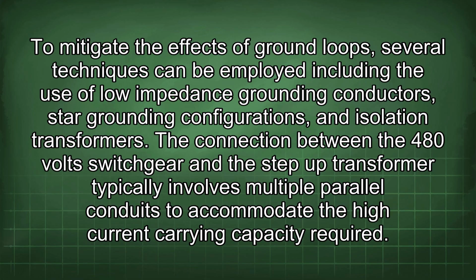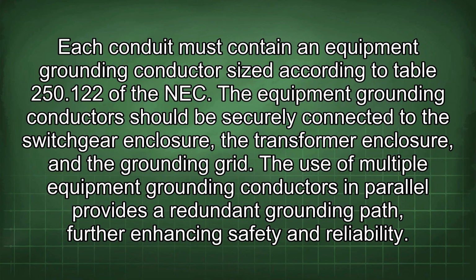The connection between the 480-volt switchgear and the step-up transformer typically involves multiple parallel conduits to accommodate the high current carrying capacity required. Each conduit must contain an equipment grounding conductor sized according to Table 250.122 of the NEC. The equipment grounding conductors should be securely connected to the switchgear enclosure, the transformer enclosure, and the grounding grid. The use of multiple equipment grounding conductors in parallel provides a redundant grounding path, further enhancing safety and reliability.